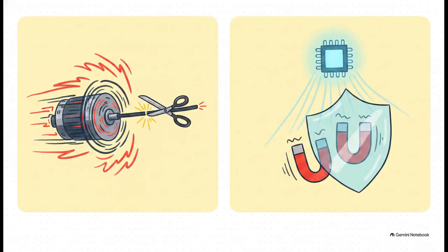But the ultimate proof? That's the demagnetization and algorithmic takeover test. Engineers deliberately run the motor at a blistering 12,000 RPM under a maximum heat load of over 130 degrees. Then, they just intentionally sever the physical sensor connections, literally cut them off. The backup software has to realize the sensors are gone and seamlessly take control using those patented search coils and algorithms in under 5 milliseconds. And it has to do it with less than 5 Newton meters of torque fluctuation. They also trigger a high-speed active short circuit, just to prove the system can clamp the peak voltage below 720 volts and the current below 550 amps, without causing any irreversible demagnetization or physical burning to the magnets.